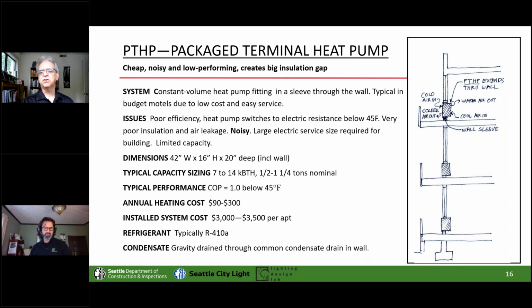Right. So they're loud. They are just a toaster oven when it gets below 45 or so, for most of them. And the sleeve around the edge, maybe they'll do a good job on the first time they install of sealing things in, but over time, they do have to get removed annually to get filters cleaned and pop back in. That little gap between the unit and the sleeve will be a major air leak. And you're talking about the exterior air intake filter.